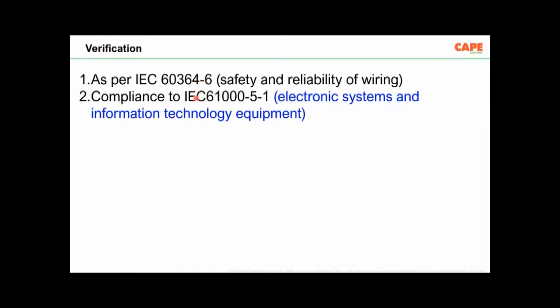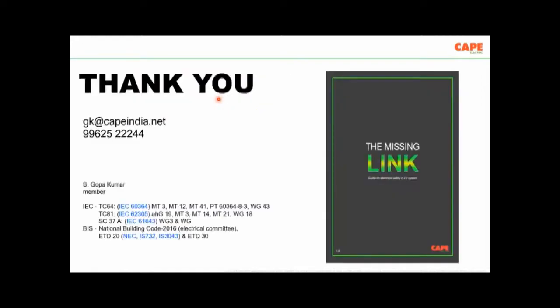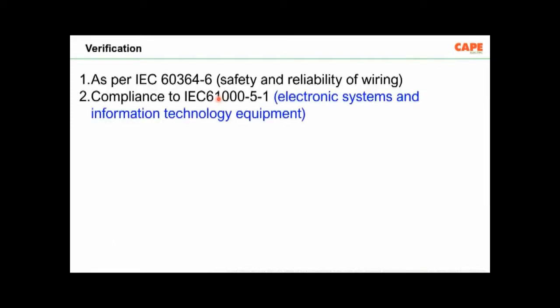The situation is similar for the EMI test. Mostly we are not following it. So basically what I wanted to tell you is, in order to have a highly reliable electronic system, highly reliable in the sense not even from the EMP point of view, but an electronic system which is protected from normal situations, like a fault from a high voltage line should not affect the low voltage electronic equipment, a lot of basic safety measures are necessary. But unfortunately, in our electrical systems, are we following those things? If I ask the question, most of the time it is not.